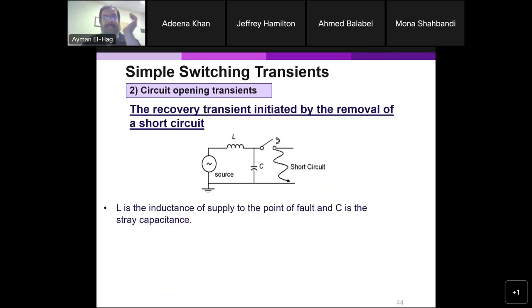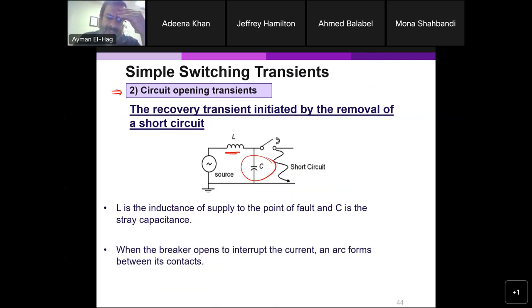So that is the second type of switching, when we have an opening transient. When we have the capacitor bank, we have a closing transient. Now we will have an opening transient. L is the inductance of the supply. C is the stray capacitance. That's not a regular capacitor. That is the stray capacitance of the system.